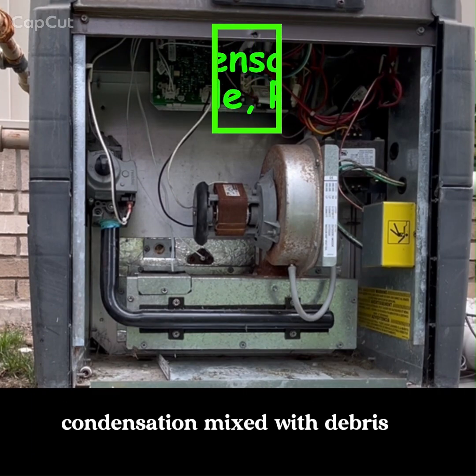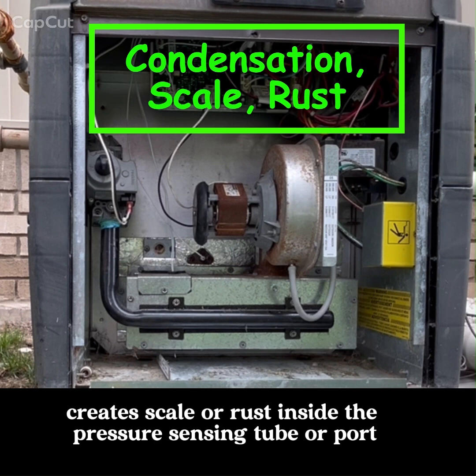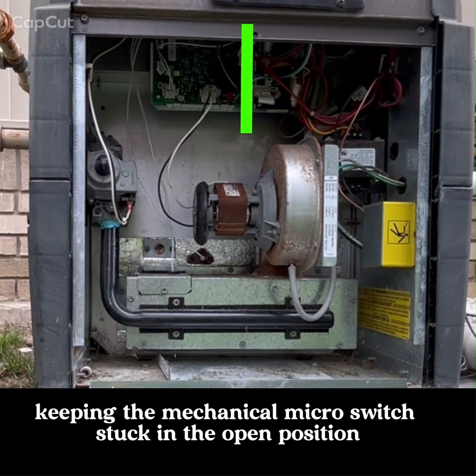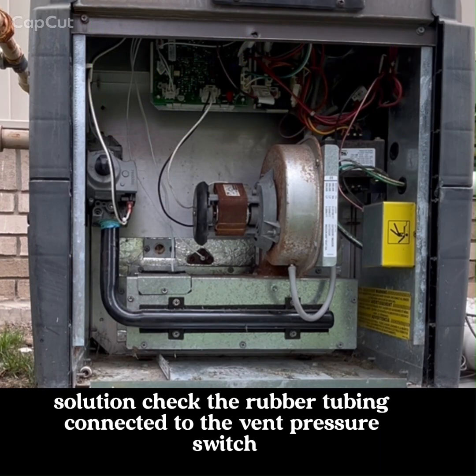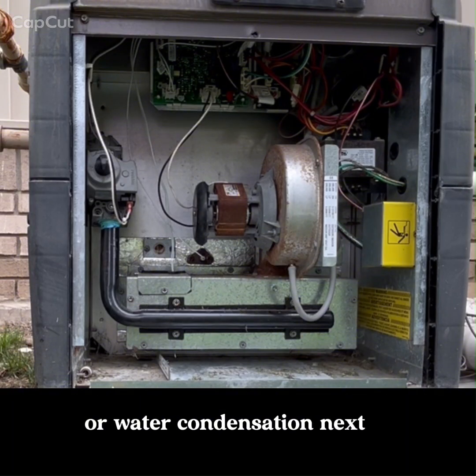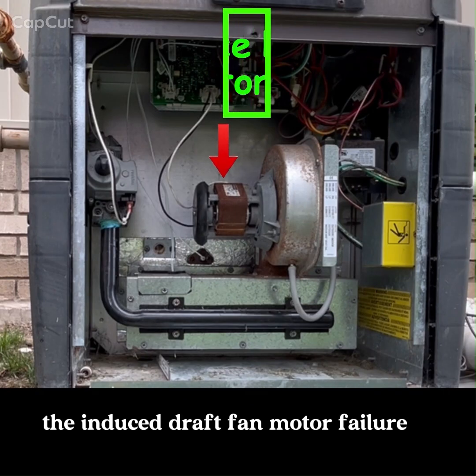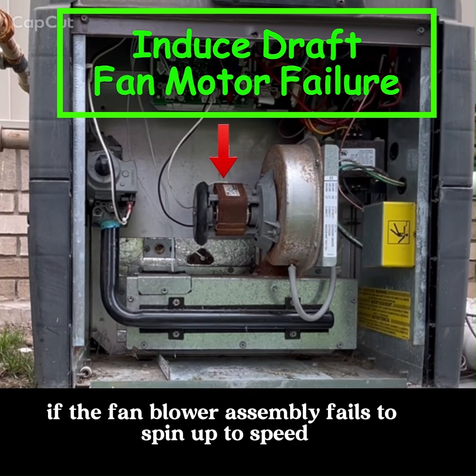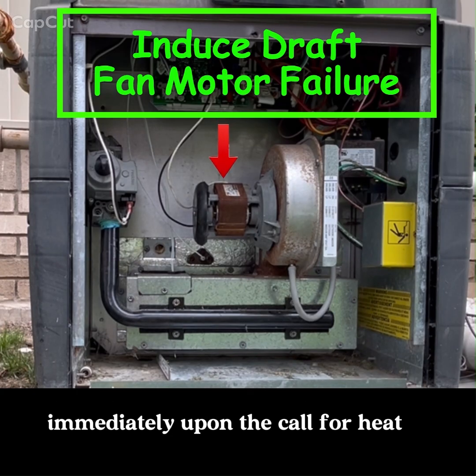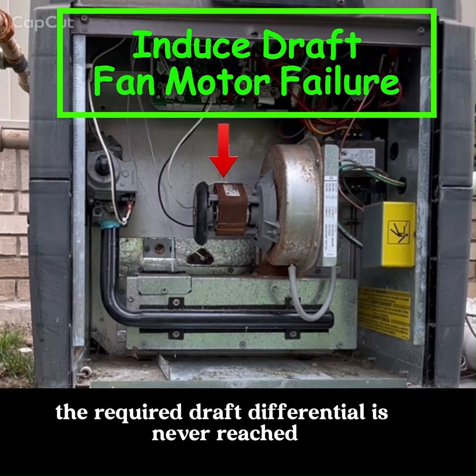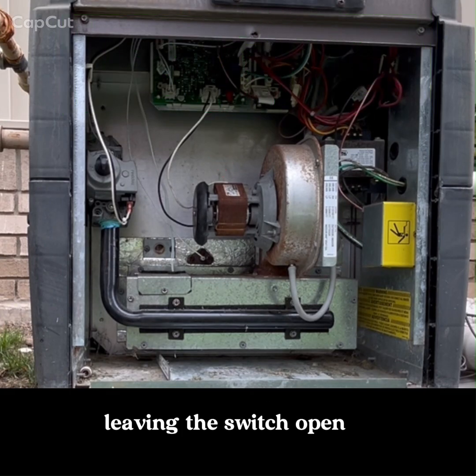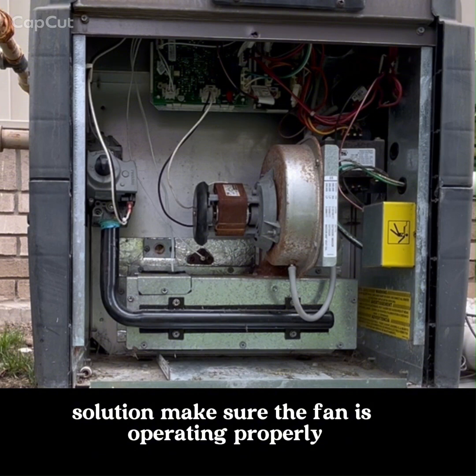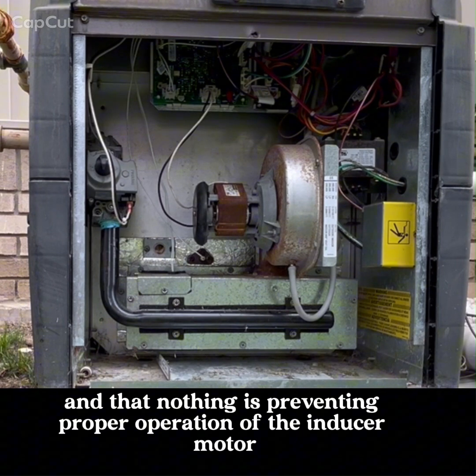Next, condensation mixed with debris creates scale or rust inside the pressure sensing tube or port, keeping the mechanical microswitch stuck in the open position. Solution: check the rubber tubing connected to the vent pressure switch for cracks, pinching, or water condensation. Next, the induced draft fan motor failure. If the fan blower assembly fails to spin up to speed immediately upon the call for heat, the required draft differential is never reached, leaving the switch open. Solution: make sure the fan is operating properly and that nothing is preventing proper operation of the inducer motor.